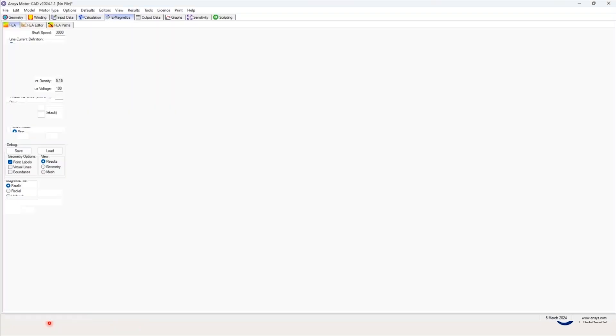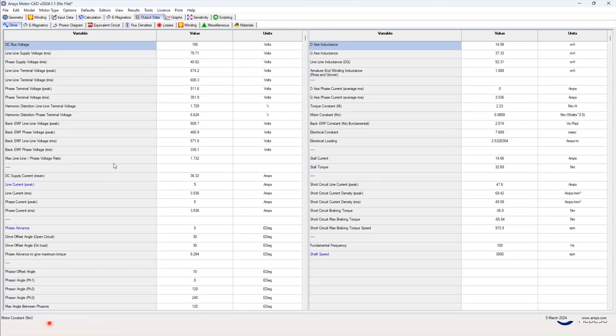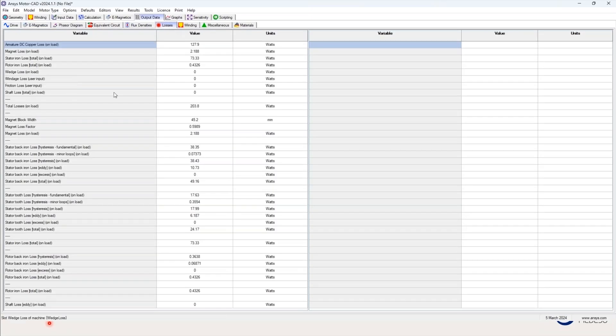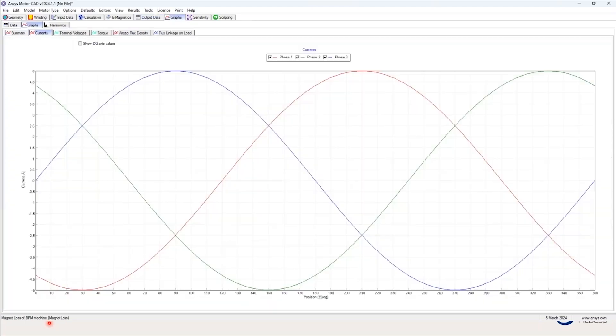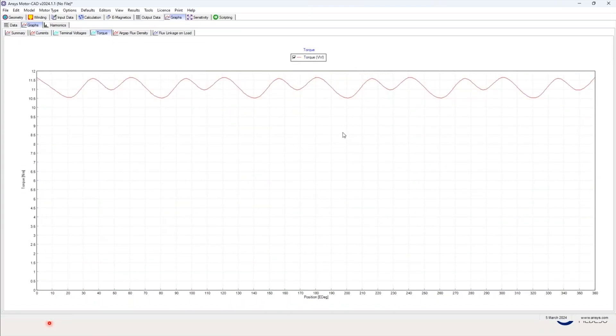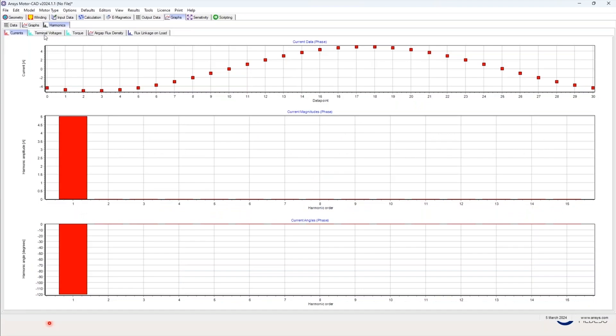Now that solving is completed, you can see the field plots in the design. We can see the output data — the most relevant things here would be the back EMF, the harmonic distortion, the phase voltages. In the electromagnetic results you can see the torque, the torque ripple, and the power factor. You can also see the losses — how much iron loss you have in the stator iron and rotor iron. You can see graphs for the terminal voltage and torque, and all the information you need for your electromagnetic analysis is there, including the harmonics.